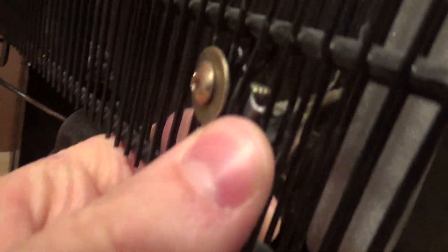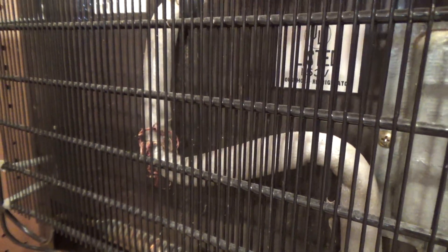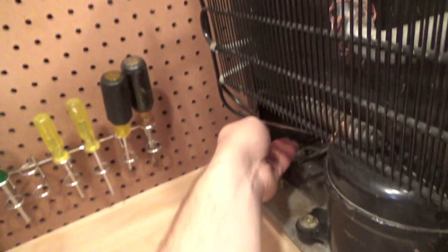Same thing here — this obviously is not supposed to be bent in like that, but it's not going to affect it at all. The condenser is getting warm already. One thing that doesn't quite make sense is why the low pressure side is a bit close to the heat of the condenser, but this is quite warm already. Yep, working good — ice cold, very nice.